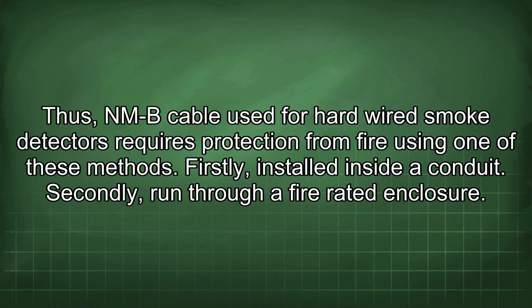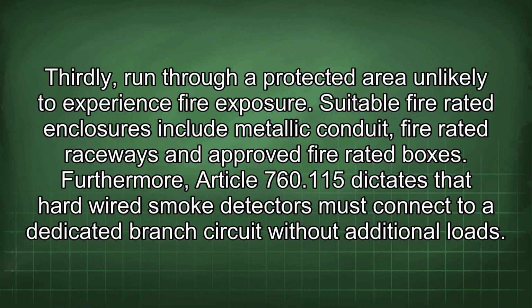Thus, an NM-B cable used for hardwired smoke detectors requires protection from fire using one of these methods. Firstly, installed inside a conduit. Secondly, run through a fire-rated enclosure. Thirdly, run through a protected area unlikely to experience fire exposure. Suitable fire-rated enclosures include metallic conduit, fire-rated raceways, and approved fire-rated boxes.